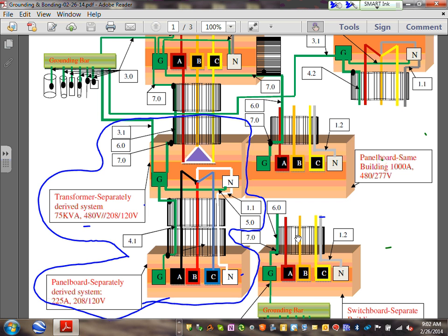That's what I'm sizing. What I sized, guys, is first the neutral right here. Then we size what is called the grounding conductor, then the system bonding jumper. Then I size the grounding electrode conductor at the separately derived system, then the equipment grounding conductor coming to the primary, and then the equipment bonding jumper on both sides. That's where you bond the conduit. Can you see that? You bond the conduits on both sides here. And the last thing we did is the supply side bonding jumper at the separately derived system.